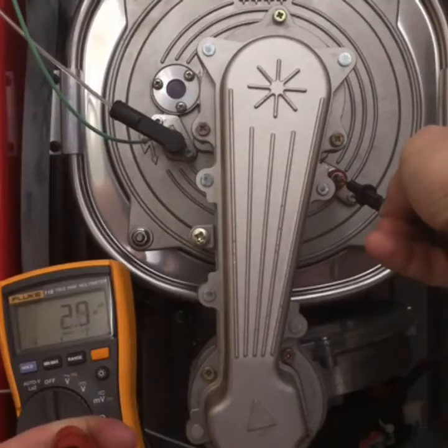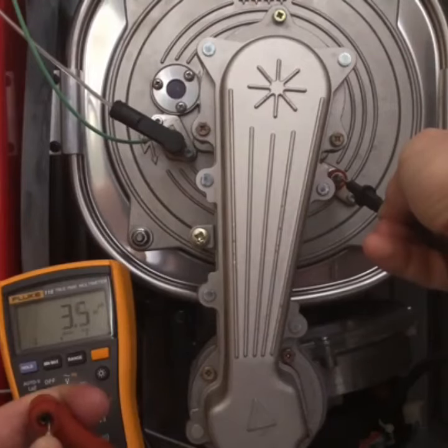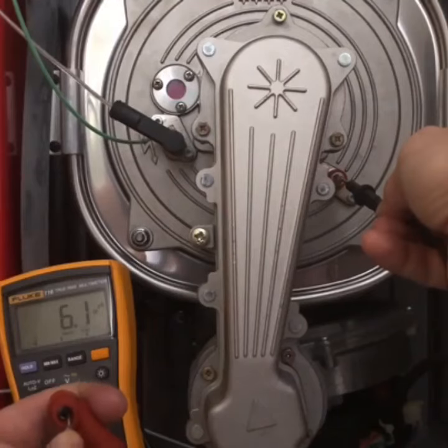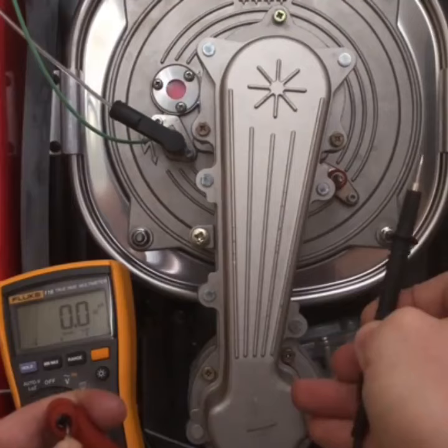When the boiler fires, the flame has an AC voltage. The flame sensor rectifies that to DC, and that's what the PCB is looking for. On this boiler, it's between five and eight microamps, and you can get that information from the manufacturer.